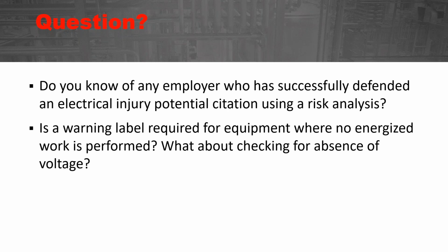Well, it goes on to read, if this equipment is likely to require examination, adjustment, servicing, or maintenance while it's energized, it has to be marked with a label containing the information in 130.5H. Which is things like the voltage, the arc flash boundary, and then one particular item, either incident energy at the working distance or PPE category, but not both. You've got to be real careful of that. The new labels that I've seen from the software companies are complying with that. I've seen for years labels that are more than 5 or 6 years old that do not comply with that.